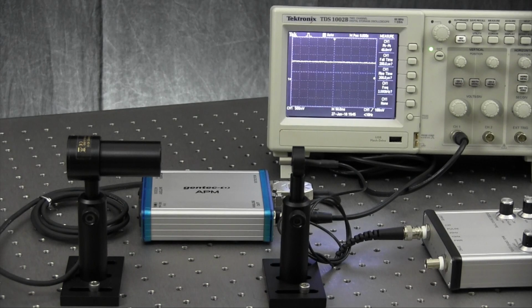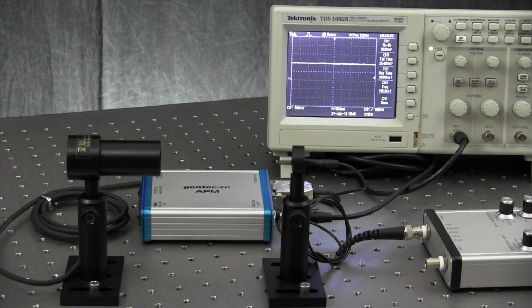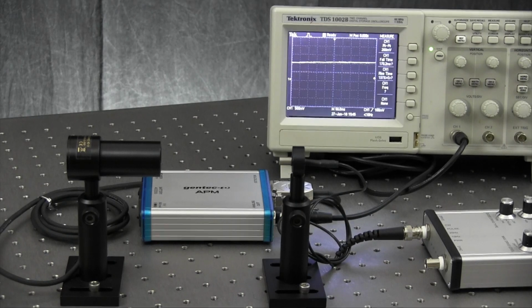Now let's consider using the UM9B without a transmissive window. I've removed the quartz window from the probe. I've set the scope range to 500 millivolts per division. As you can see, the voltage baseline is not stable. Why? It is because air currents in this lab have the effect of changing the detector's temperature, which results in generating a voltage. In addition, the windowless probe will now respond to thermal background in the lab.